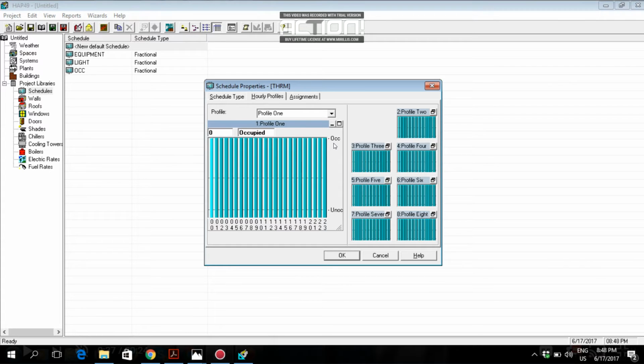The thermostat will switch the machine on and off depending upon the set point of the area. For example, if you set the point at 20 degrees centigrade, with minimum temperature 20 and maximum temperature 24 degrees centigrade, once the room temperature reaches 20 degrees, the thermostat will turn off the machine because you don't want further cooling.